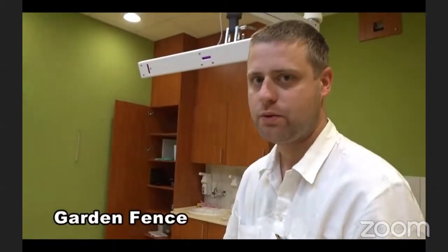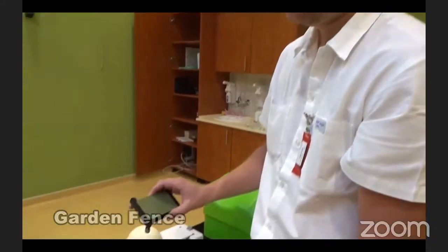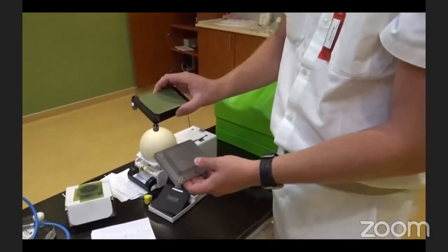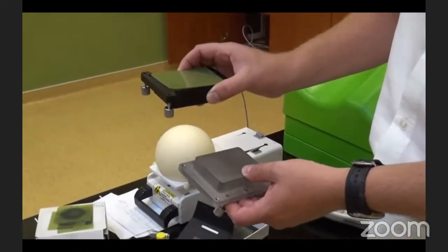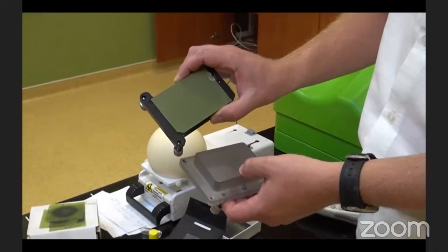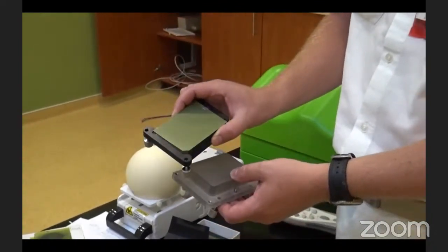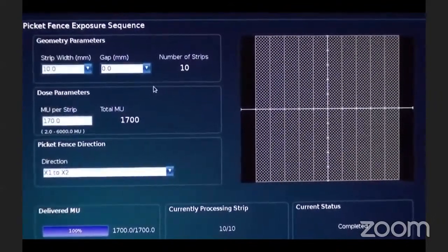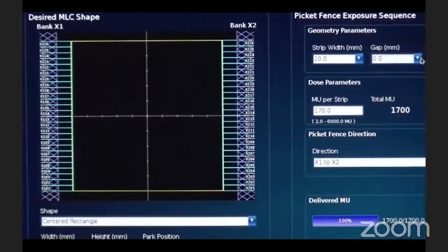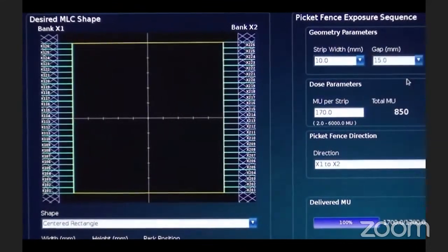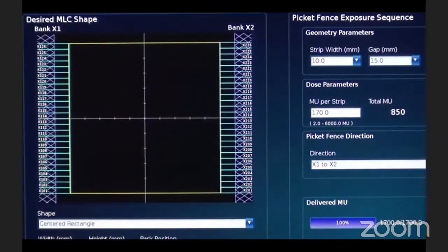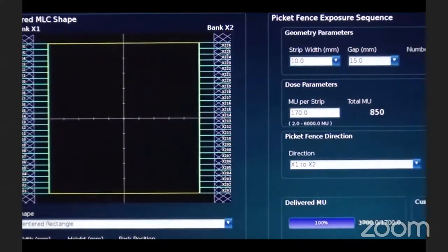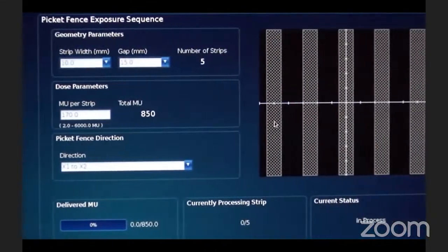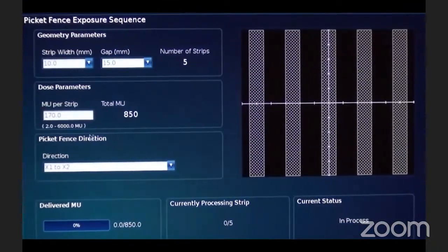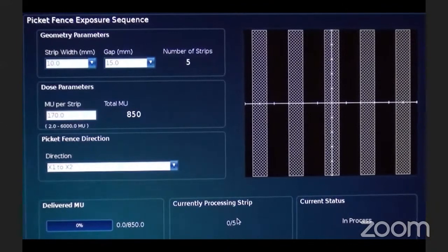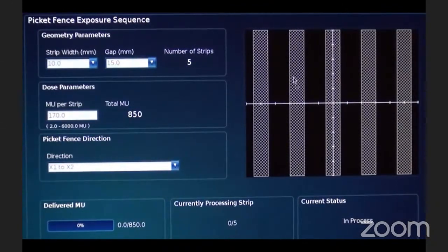For the garden fence test, we are using the same positioning device as for picket fence, but we will deliver different kinds of beams, and this is a monthly QA, not a daily QA, for checking the calibration of the MLC motors. The garden fence test is very similar to picket fence, but here we are applying 15 mm gaps between the fields, so we deliver only 5 beams. For each beam we deliver the same 170 monitor units, so nearly 1.7 gray, and we will evaluate these 5 fields with the software.